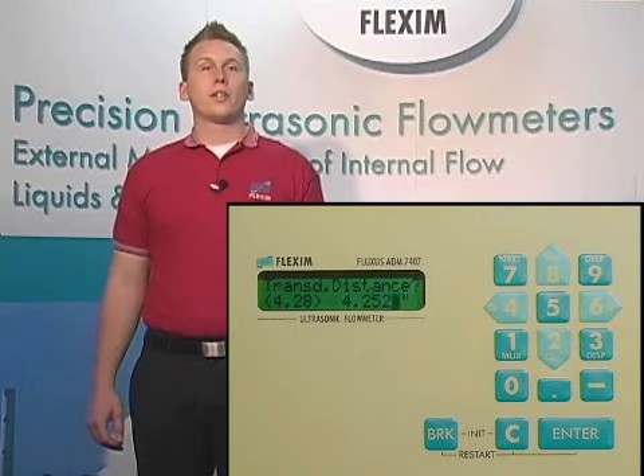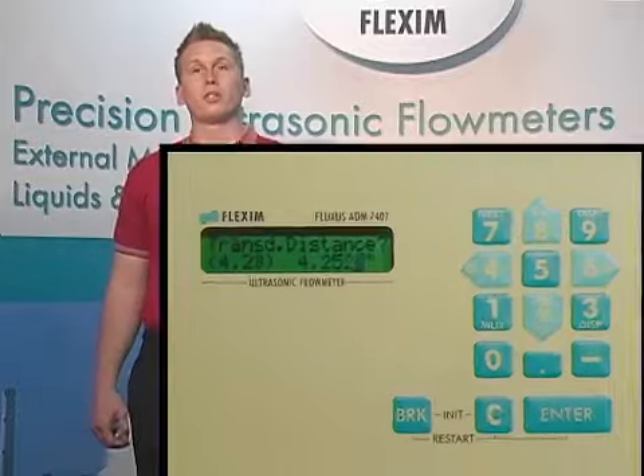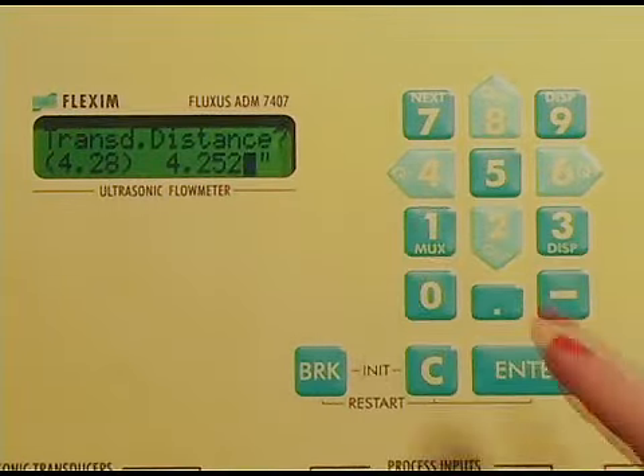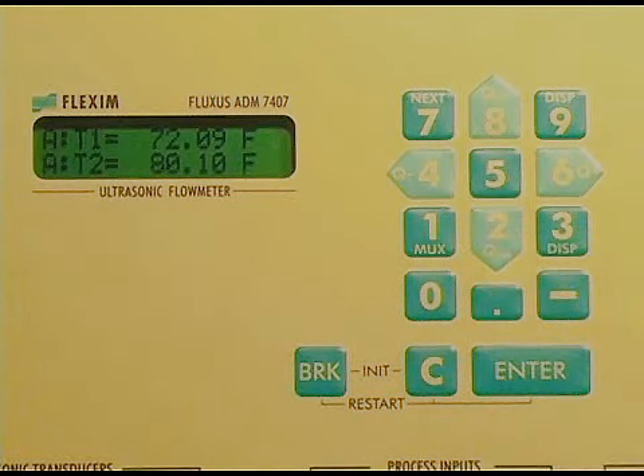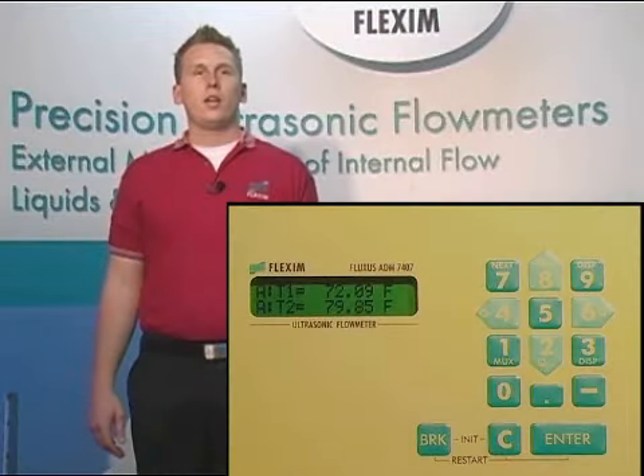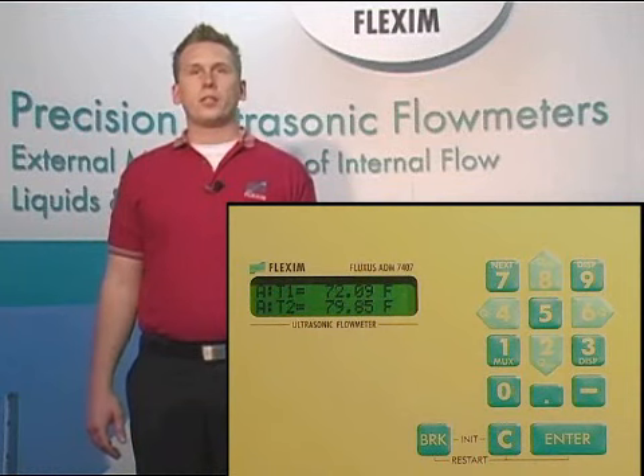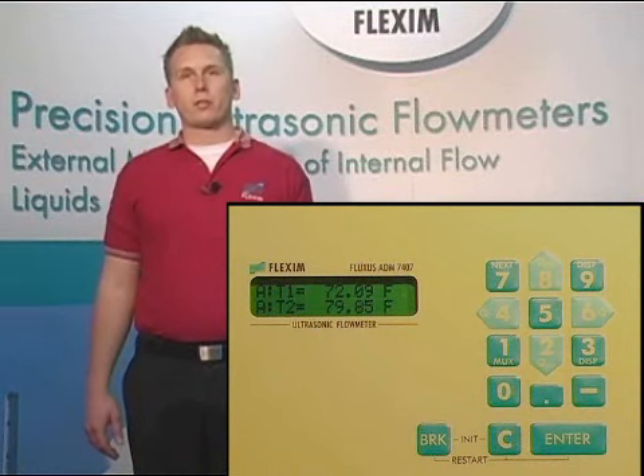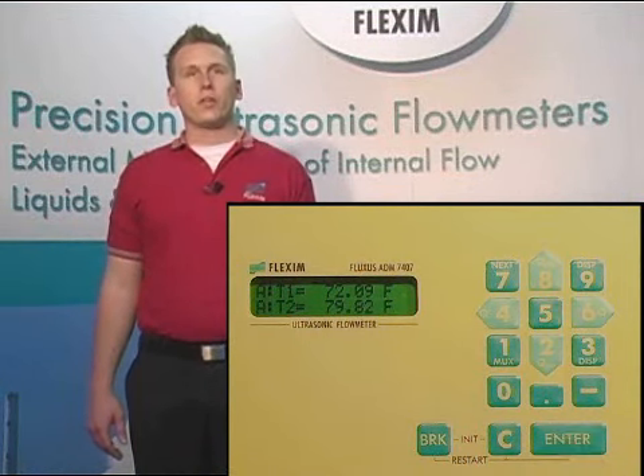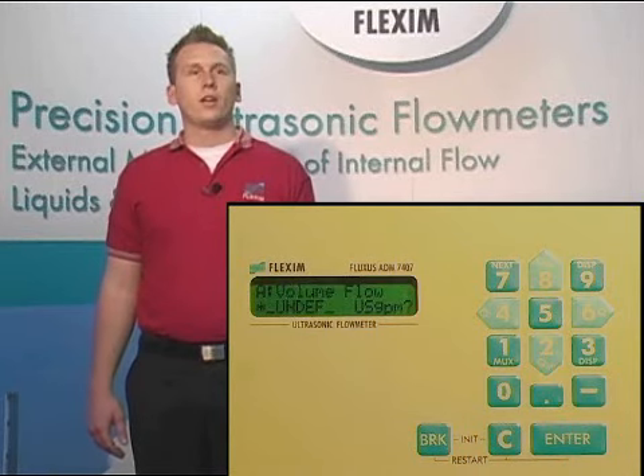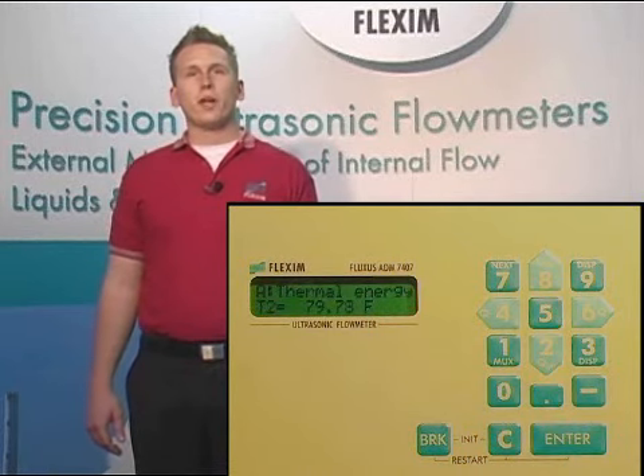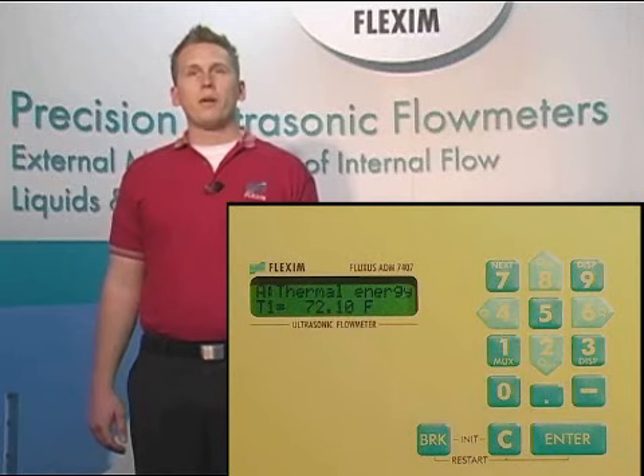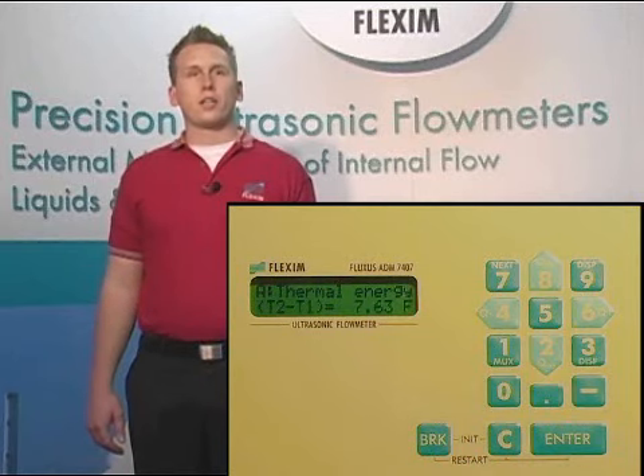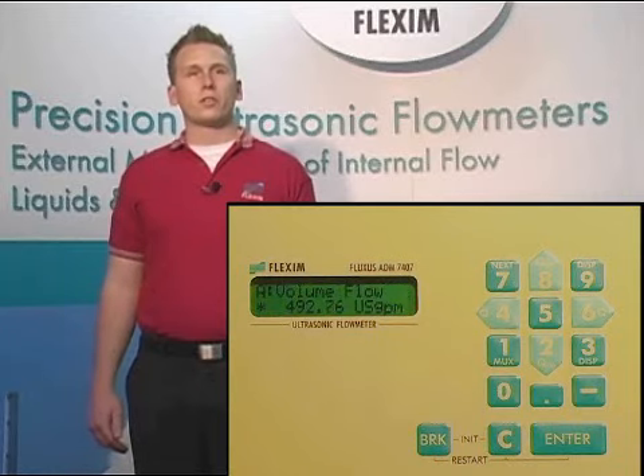Now we get to tell the meter exactly how far apart we actually put our transducers. Input the actual distance we placed the transducers at, and hit enter. Lastly, we have a prompt for the temperatures T1 and T2, and we can verify that they're correct. If we simply hit enter one last time, we're measuring. And now we're done. We're reading thermal energy on our line. You can play with the 9, 3, and enter keys to check diagnostics on your measurement. For full details of how to do this, please watch video number 12.